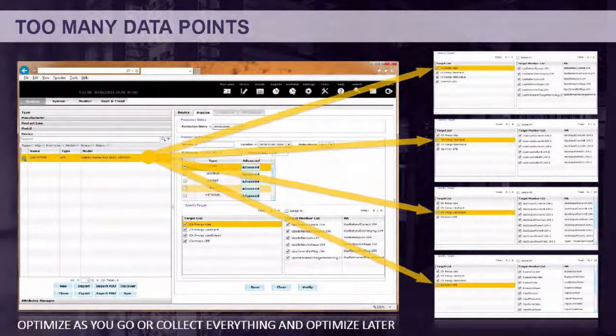This is an example of a UPS. It has, I think, 30 different points of data, but from the perspective of my operators using this system, they need 3 to 5. Ninety-nine percent of the time they don't need the rest of the data. And if they're in a situation where they need that very obscure data point, they're not looking at the DCIM system anyway, they're going straight to the device.